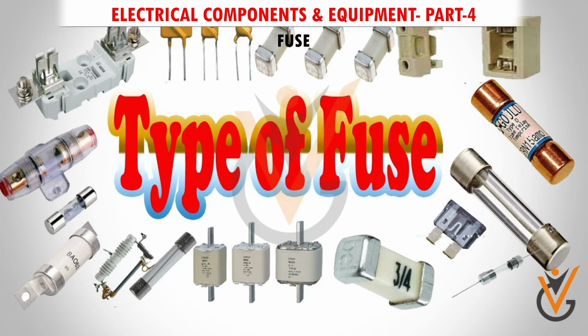Fuse. It is the most common and important type of safety device used for domestic and commercial installations. These fuses are of KitKat type and are also known as cutout. These cutouts are made of porcelain in current ratings of 15 to 300 amperes. The materials used as fuse wire are tin, lead, silver, antimony, copper and aluminium etc. Copper or lead-tin alloy is mostly used in ordinary fuse wire.